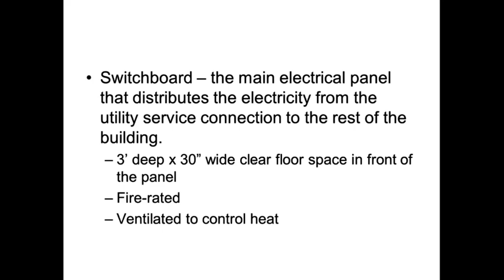And it has to be fire rated. A lot of times you have to have ventilation to control the heat, because sometimes there's heat buildup in a panel. This is very true when it comes to a commercial facility. So what we've got to do is always make sure you have that room in front of the panel or the switchboard.